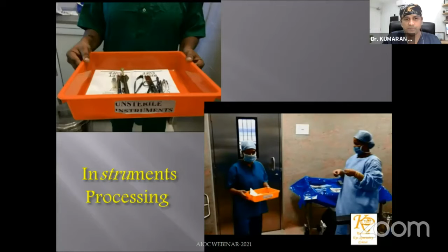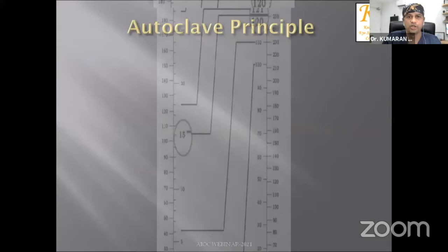The instruments then should be processed in an ultrasonic cleaner so that all the blood and body fluids are separated, and then you follow the 3-bin technique where they are scrubbed sequentially in distilled water preferably before they are cleaned, and they are air dried before they are packed. Packing should be done in either 3 forms, either with linen, paper plastic pouches, or non-woven paper as per the GSM listed here. It is a good technique to place all the trays vertically as shown here so that there's steam penetration all around.